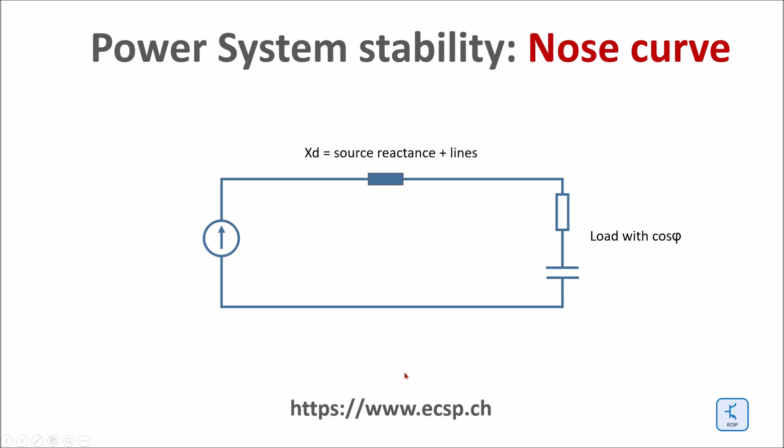Here are the very basic parameters and models needed to derive the nose curve. There is a source and there is a load, and between the source and the load we have a reactance which is the source reactance and possibly some line reactances. The load may have a constant cosine phi and it is variable. The nose curve is an interaction between the variable load, the source voltage E, the load voltage V, and the voltage across the reactances between the source and the load. The voltage across XT is directly proportional to the current through the load.